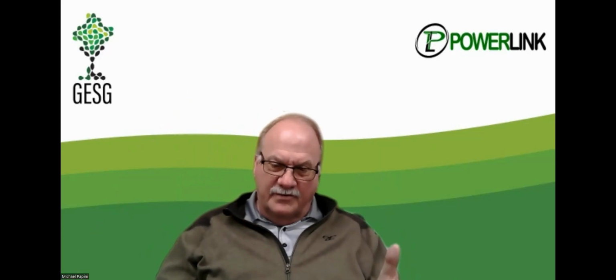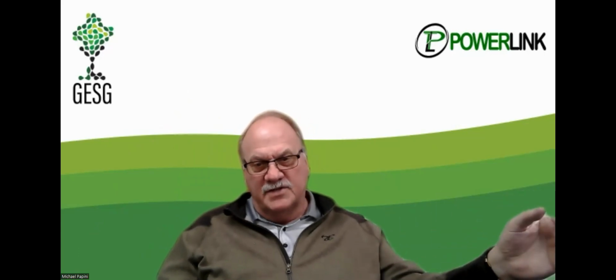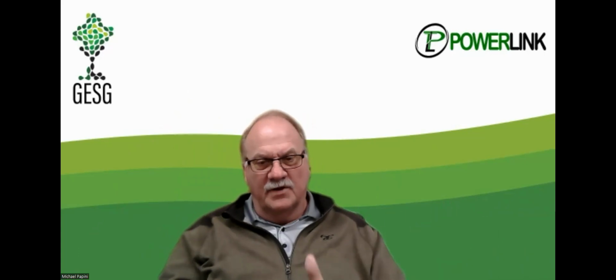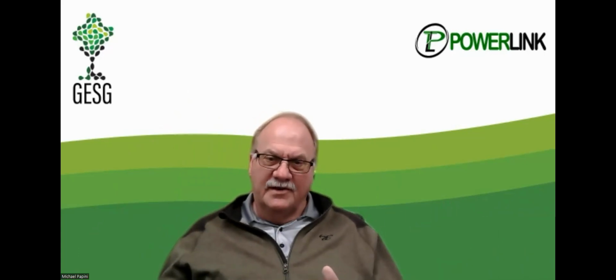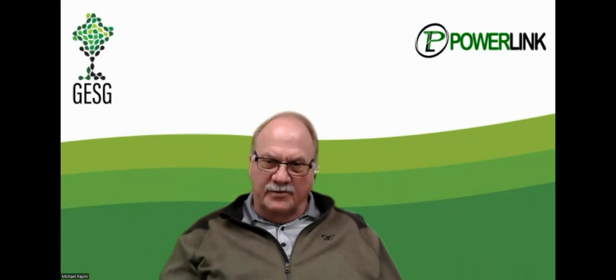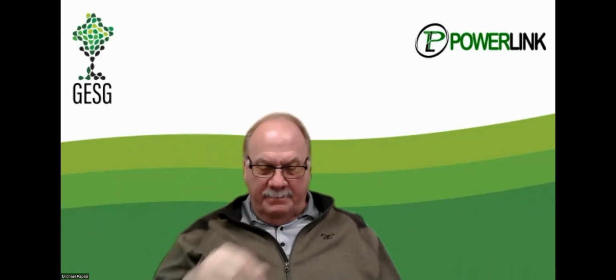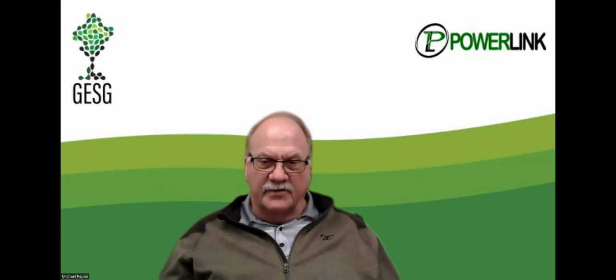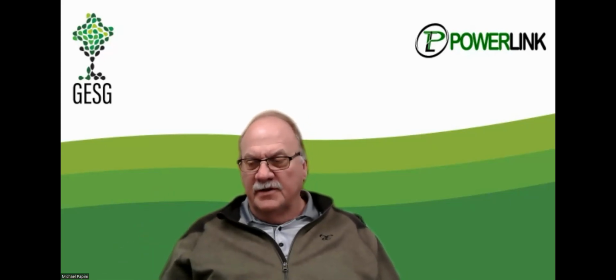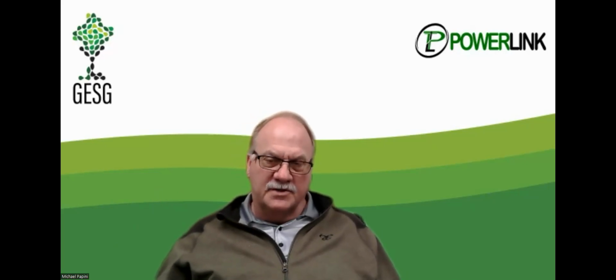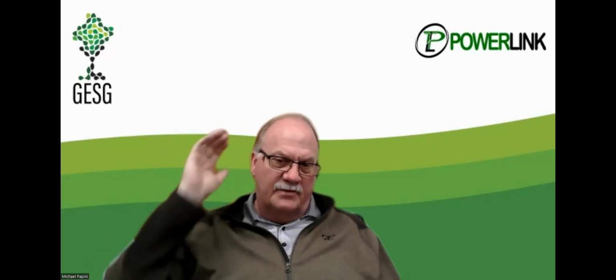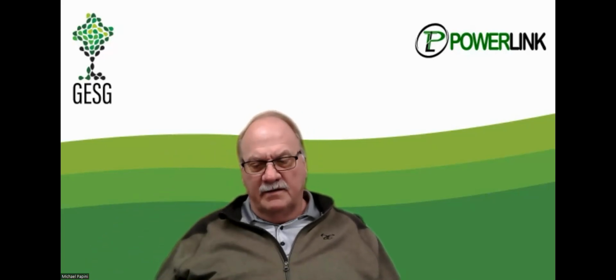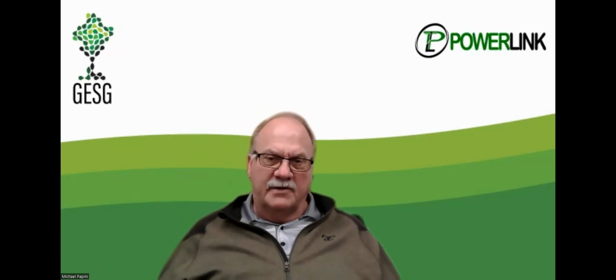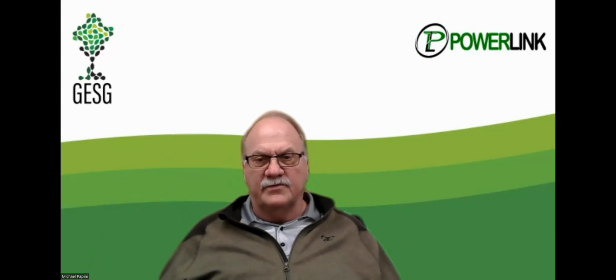I said it's because as it's installed back toward the source, the dynamics change, everything in front of it still needs that kVA. They were also having problems with a capacitor bank that kept shorting out because of harmonics in that building, they had a lot of robots and stuff in there. So we went in and did load correction for the whole facility, and pretty much did away with that capacitor bank. They're fine now. As a matter of fact, they just called, they added some other equipment, and they want us to come out and put a couple more boxes in on the new stuff.